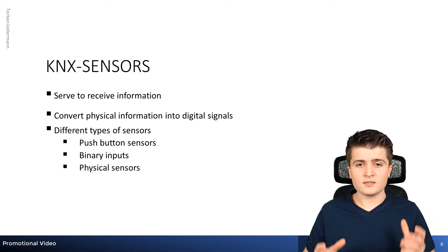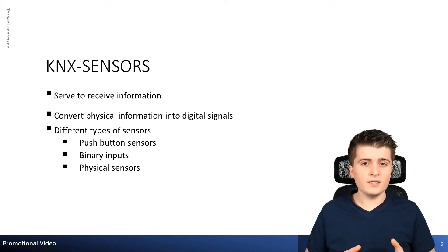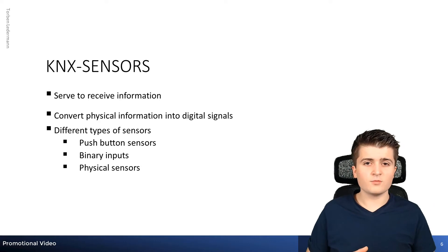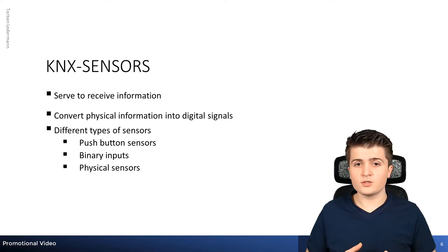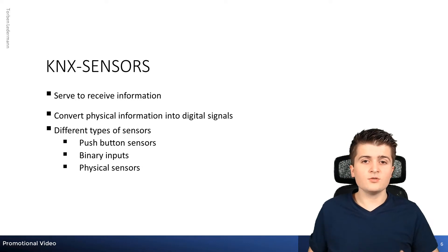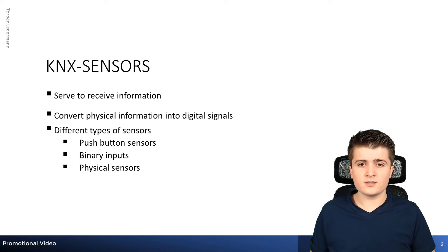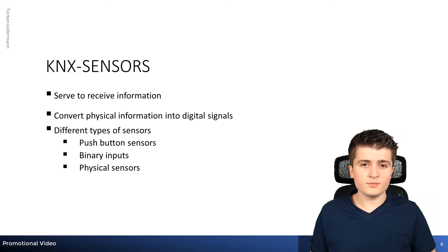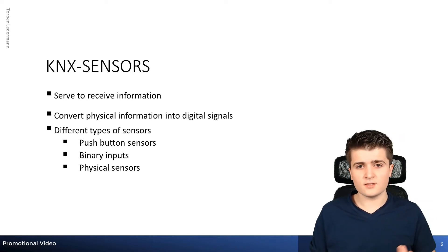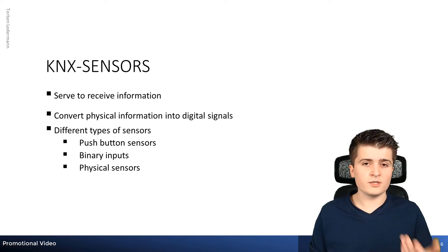Another big group of sensors are the so-called binary inputs. With binary inputs you are capable of converting normal switching signals or conventional push buttons into KNX telegrams. So you hook up, for example, a window contact to such a binary input, and it converts that switching signal into a KNX telegram — and the same applies for conventional push buttons.